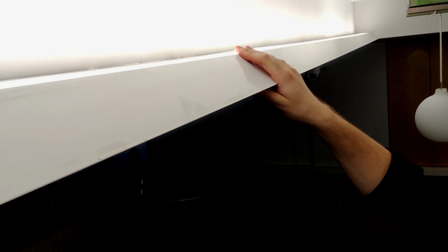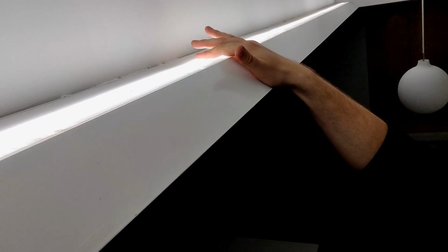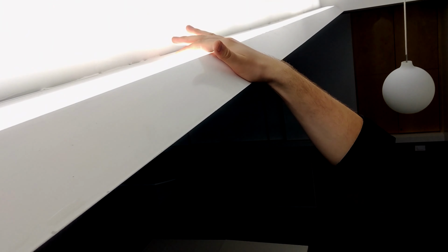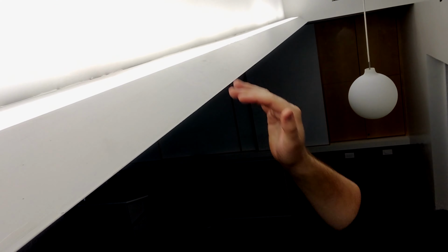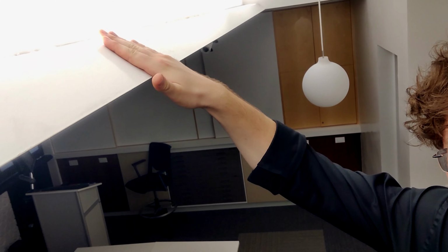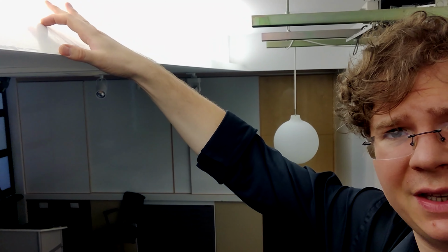It's built out of steel or aluminum. This one happens to be aluminum so that it does not warp. And then above that, this is the lens of the fixture itself. That lens is parallel with the floor, so that it is concealed. And then this angled piece, the angle itself is determined so that if someone is up against the wall, they're not going to see the thickness of this portion. They're only going to see this lower edge.